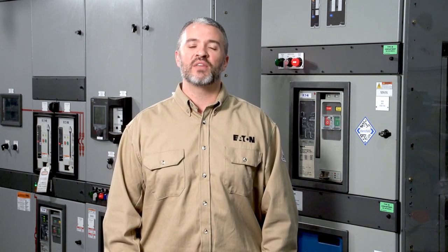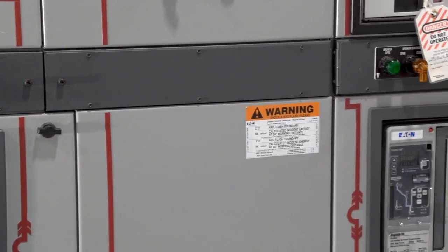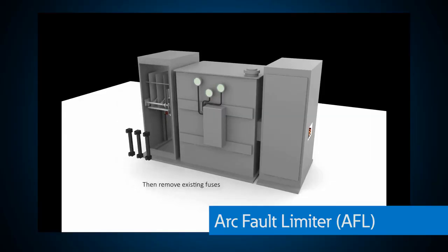This can significantly reduce arc flash energy for medium voltage systems. For most power systems, the highest level of arc flash energy on low voltage switchgear is on the source or line side of the main circuit breaker. One great option we can show you here at the PSEC is the arc fault limiter or AFL conversion.